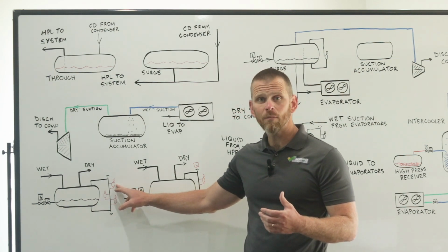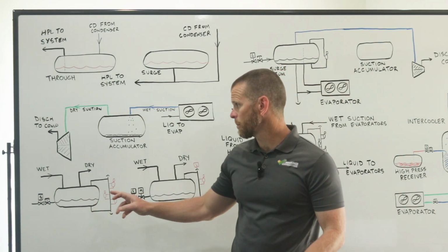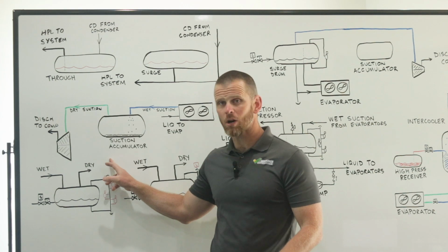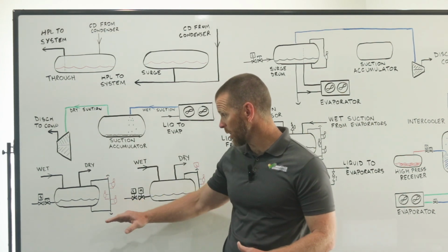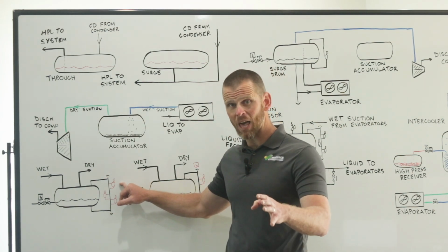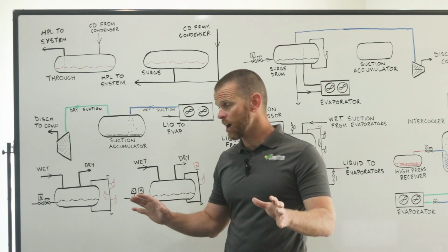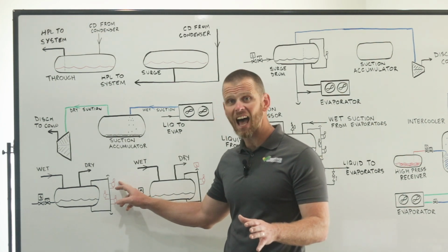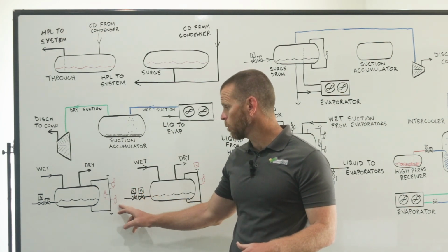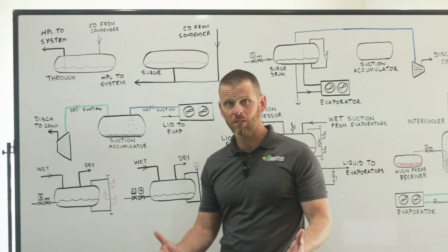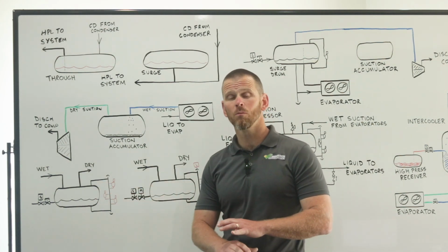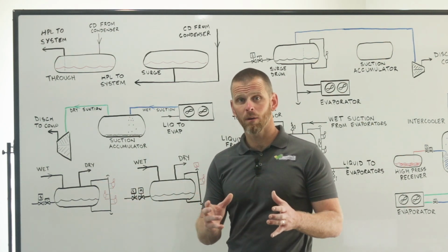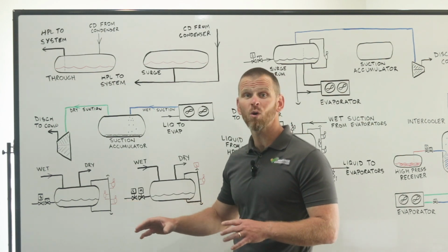The one above it is our high level float switch. Remember, we don't want there to be any liquid in our dry suction into the compressor. So if the level gets too high, we want to trip those compressors so they can't operate and get slugged with liquid. That's the high level float switch. And then the bottom one, maybe to protect the pumps. If the level gets too low for some reason, we want to protect the pumps from cavitation. We might have a low level cutout.